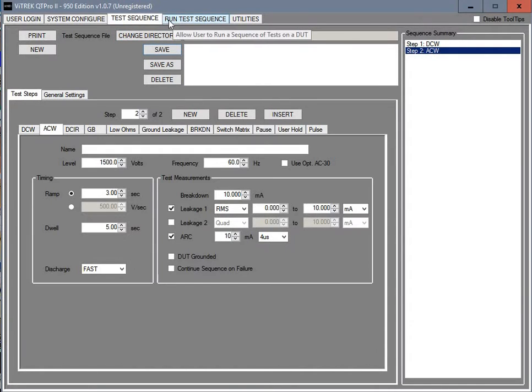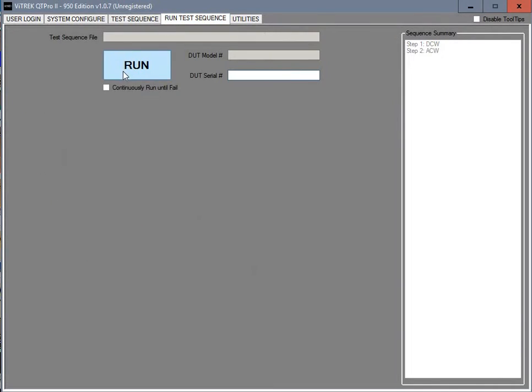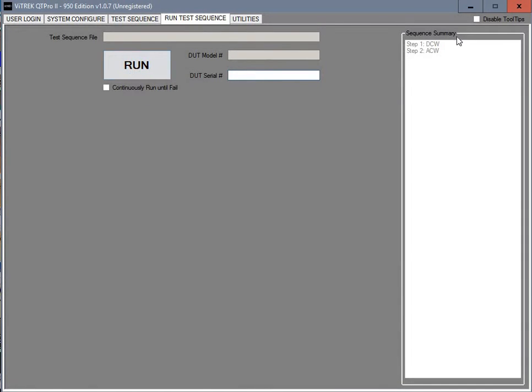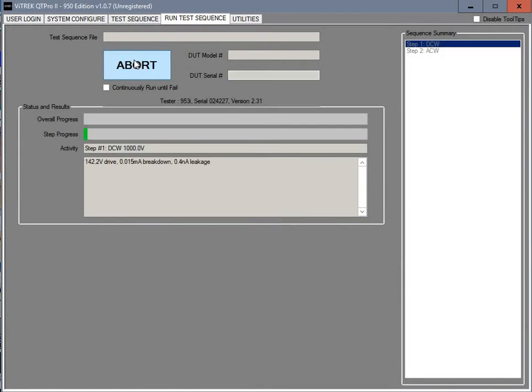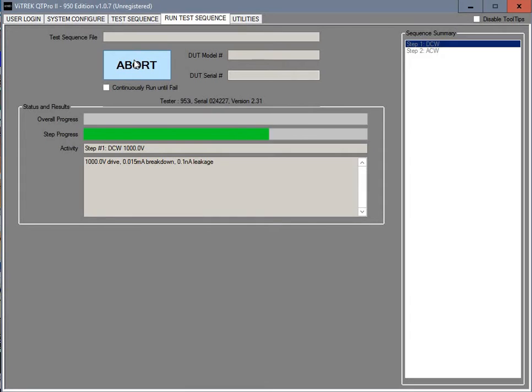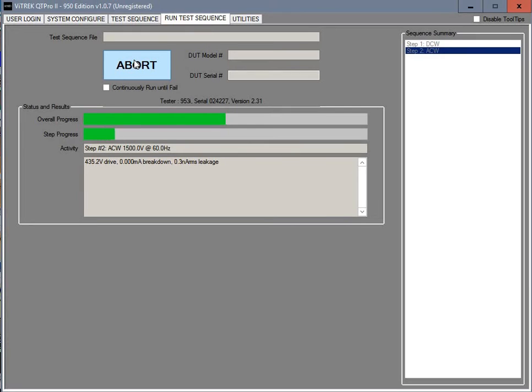Once we have that saved we can run the test. In this case we're going to run those two tests that we have right here. This is connected right now to a 953 tester. And this is the 1000 volt test at DC. And then it automatically switches over to AC and runs that test.